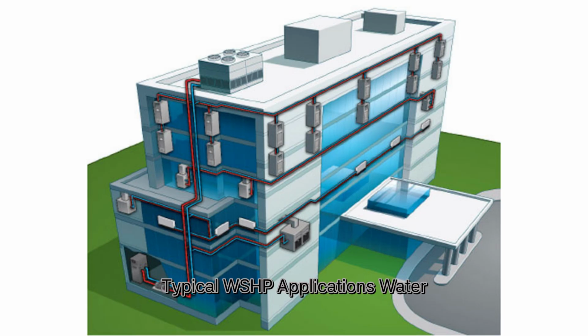Typical WSHP applications. Water source heat pump systems are flexible and fit a variety of building types. First, they're ideal for multi-story or multi-tenant buildings, where each zone needs individual control and metering for comfort and energy tracking.